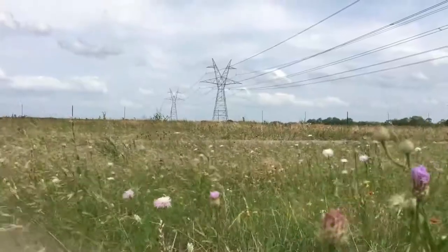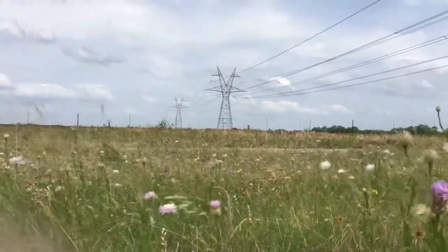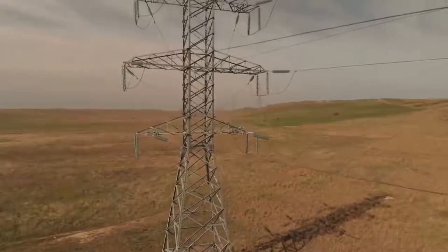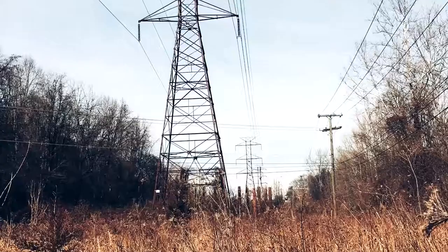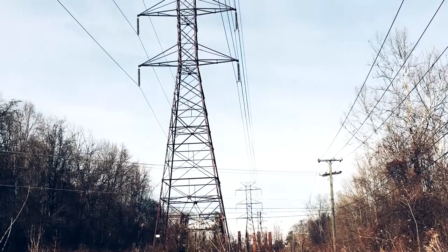High voltage isn't the only challenge associated with electrical transmission lines. Just selection of the conductors themselves is a careful balancing act between strength, resistance, and other factors. Transmission lines are so long that even a tiny change in the material or size of the conductors can have a major impact on the overall cost. Conductors are rated by how much current they can pass for a given rise in temperature. These lines can get really hot and sag during peak electricity demands, which can cause problems if tree branches are too close.